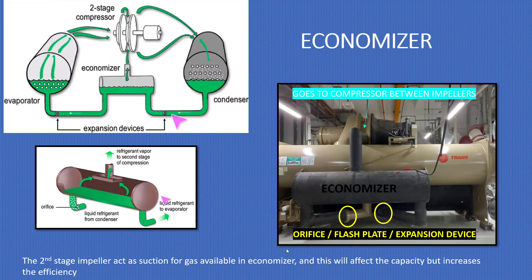The economizer is one of the most important components — it is used to increase the efficiency of the chiller. You can see here on the right-hand side the condenser and on the left-hand side the evaporator. The vapor goes to the compressor. There is an orifice through which liquid refrigerant from the condenser goes into the economizer, then starts to evaporate. Only the vapor goes to the compressor; the liquid comes back to the evaporator for vaporization. The second-stage impeller acts as suction for gas available in the economizer, which affects capacity but increases efficiency.